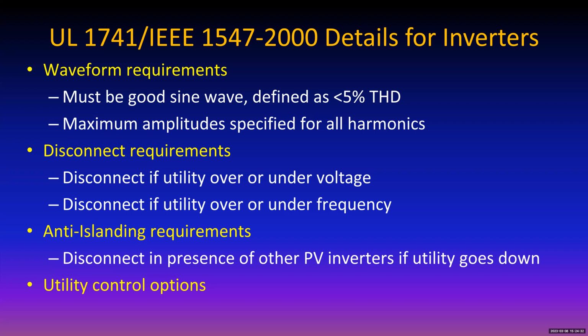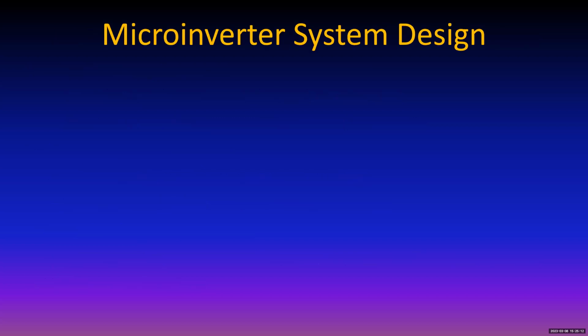So then there's also possible control options with utility. The utility, you might be able to sign an agreement. The utility can vary the power factor of your system up, say, between minus 0.8 and plus 0.8, or maybe they can turn on your batteries if you have batteries. With a straight grid connect, mostly what they want to control is your power factor, and they don't necessarily want to reduce your output. Normally, if you're cranking out, they want to use everything you have available. All right, but they might want to use you to help them do some power factor correction, because that makes their system a little more stable if you can do that.